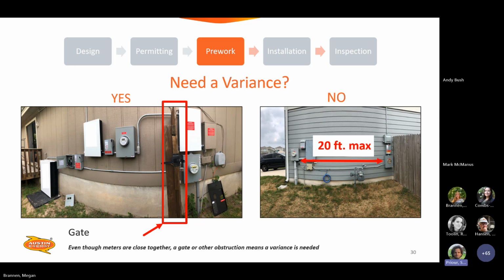Again, good morning, y'all. Stuart here. When do you need a meter variance? Meter variance being when you can't group the 2 meters, the revenue meter and the PV meter. On the left, you can see that the meters are close to each other, but there's an obstacle in the way and they're not within line of sight of each other. So if you need to do something like that, then you will need a variance. You'll need to apply for that and receive it before you install that equipment.